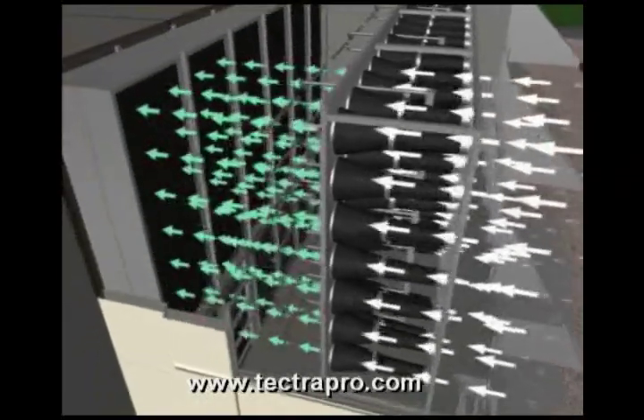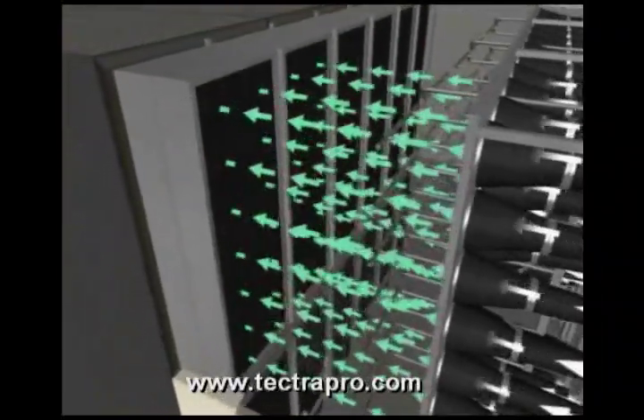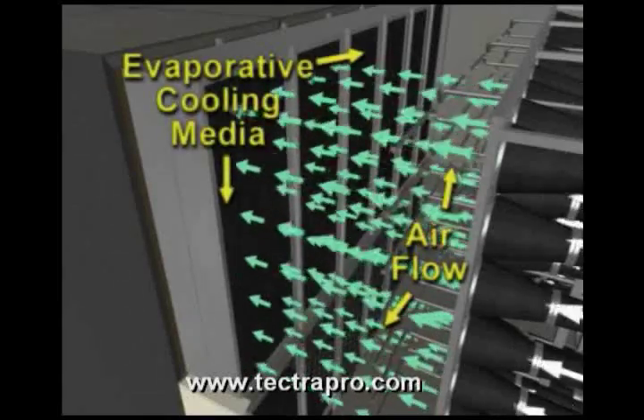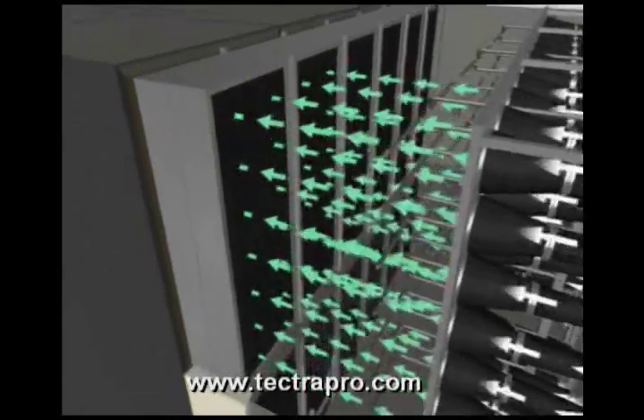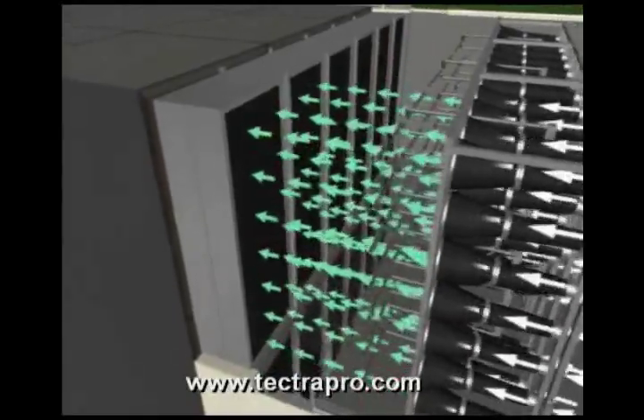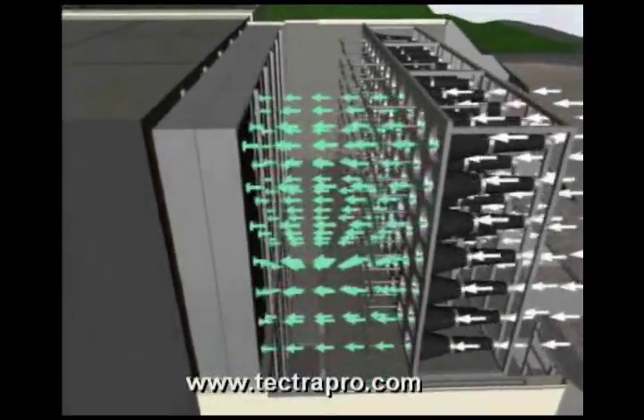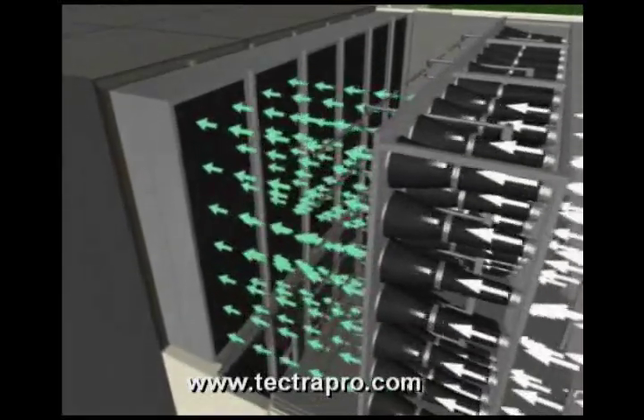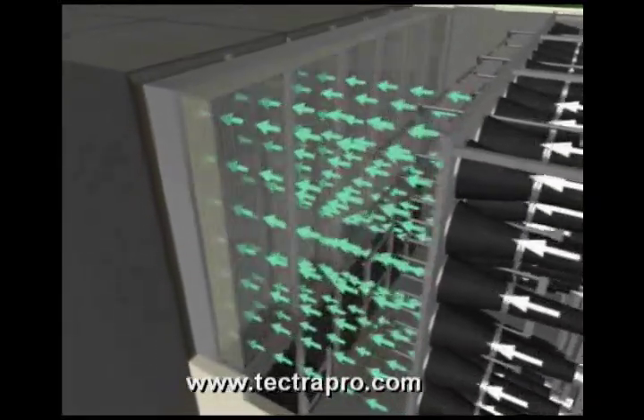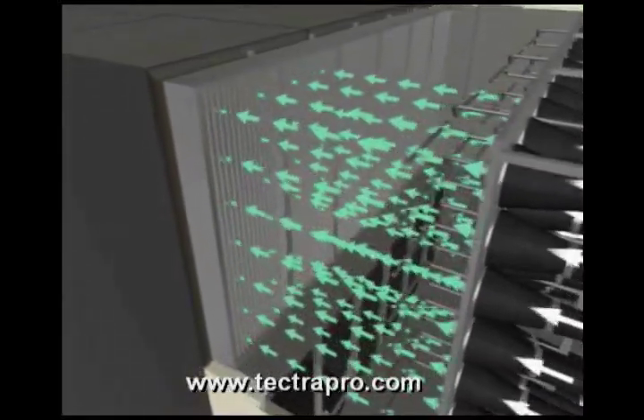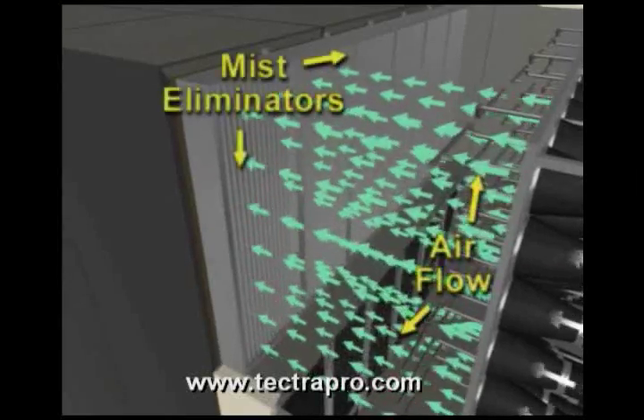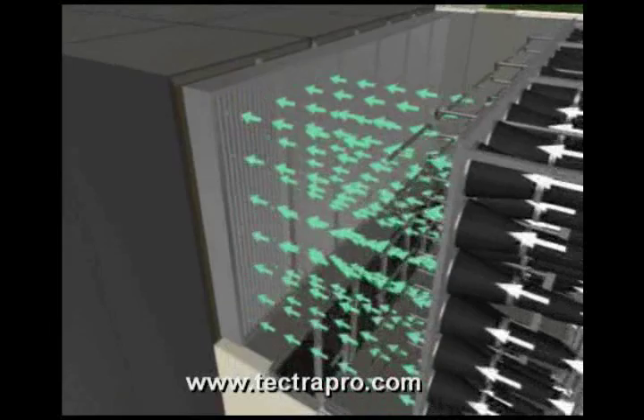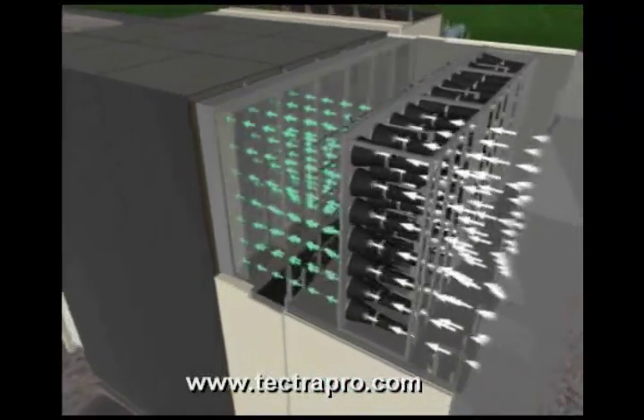From the filters, the air goes to an evaporative cooling media section. The evaporative cooler utilizes water to cool the incoming air. The cooler air results in a greater density of mass flow, thus maximizing the gas turbine's power output during hot days of operation. Downstream of the evaporative cooling section are the mist eliminators, which capture loose droplets of moisture that may be carried out of the evaporative cooler media.